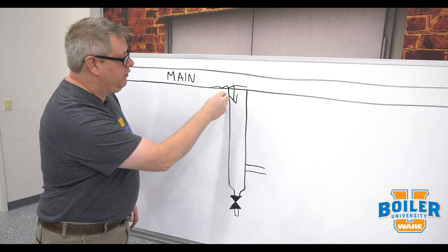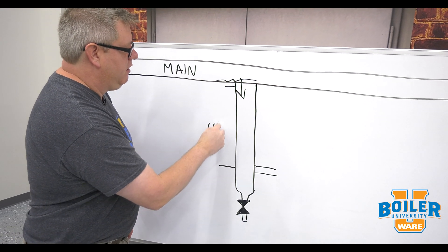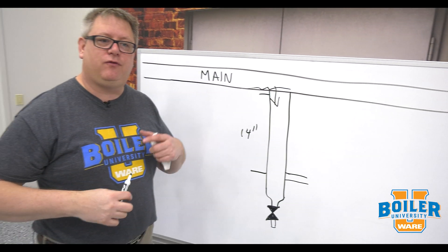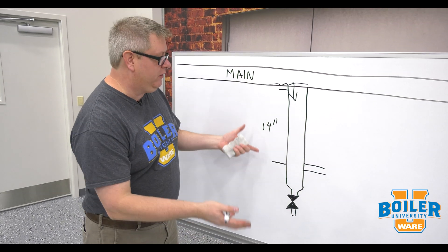The height of this drip leg typically is going to be about 14 inches. That is for a manually started up system.